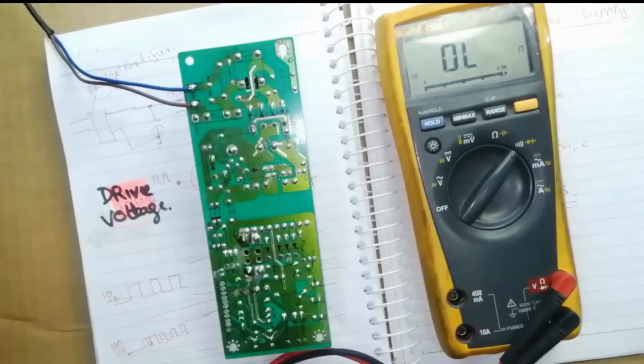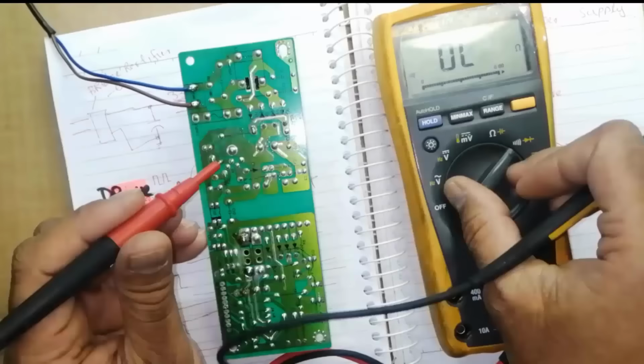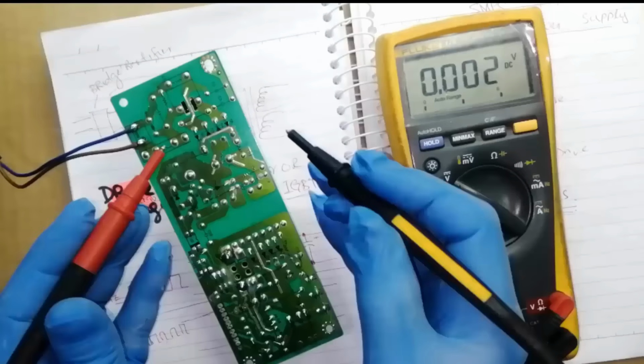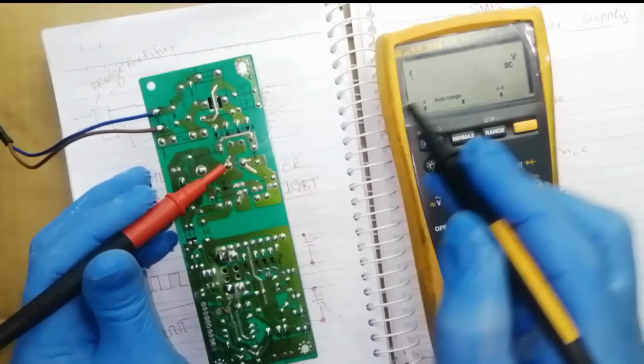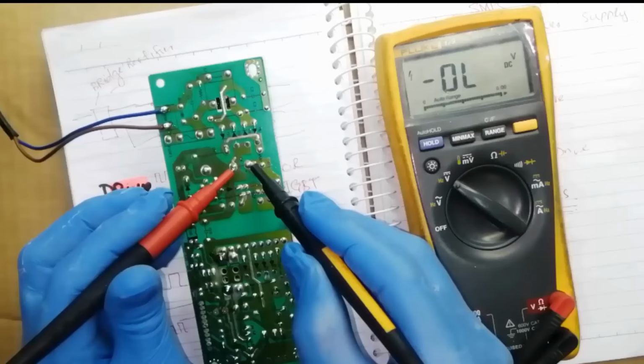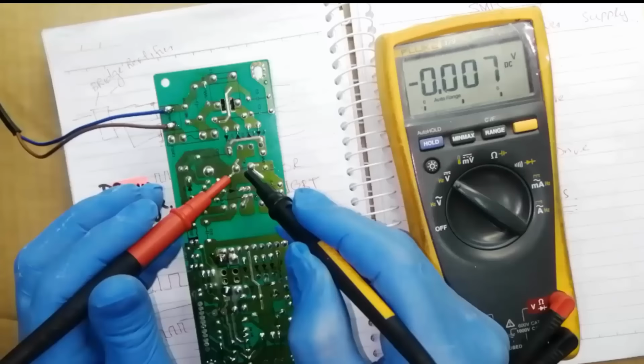Now I will connect power again, switch the meter to DC voltage and come to this capacitor. If I can find voltage here at this capacitor, it should be 337 volt. If I cannot find voltage at this point, what is the problem? The problem may be the capacitor is open inside.